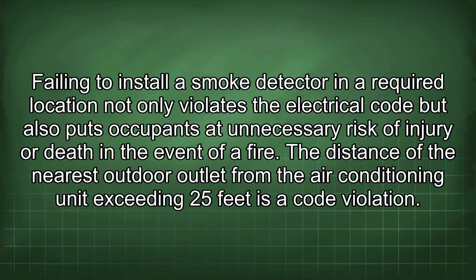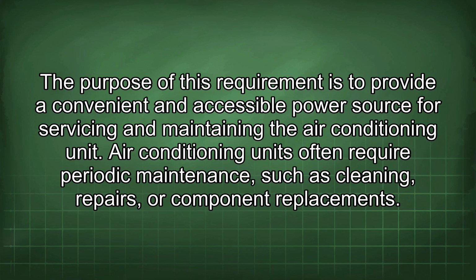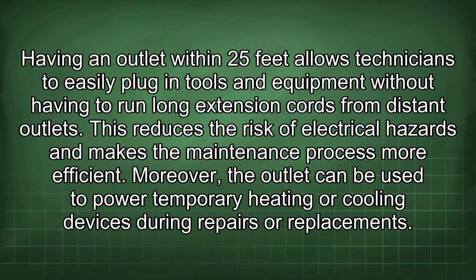The distance of the nearest outdoor outlet from the air conditioning unit exceeding 25 feet is a code violation. The purpose of this requirement is to provide a convenient and accessible power source for servicing and maintaining the air conditioning unit. Air conditioning units often require periodic maintenance such as cleaning, repairs, or component replacements. Having an outlet within 25 feet allows technicians to easily plug in tools and equipment without having to run long extension cords from distant outlets. This reduces the risk of electrical hazards and makes the maintenance process more efficient.